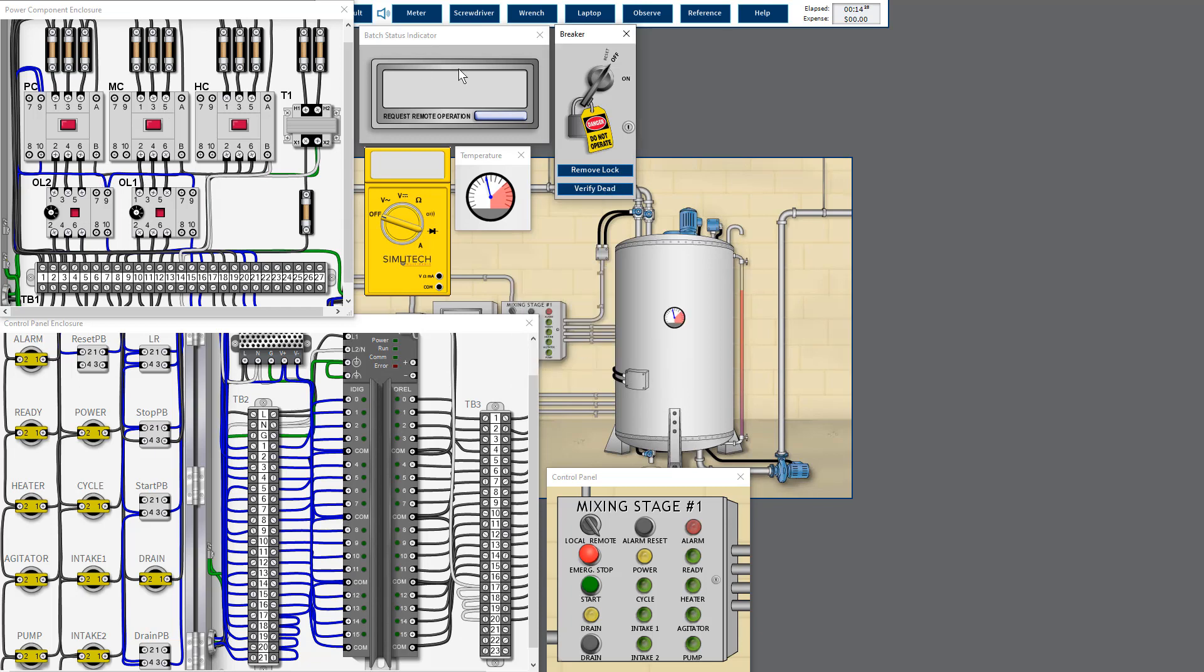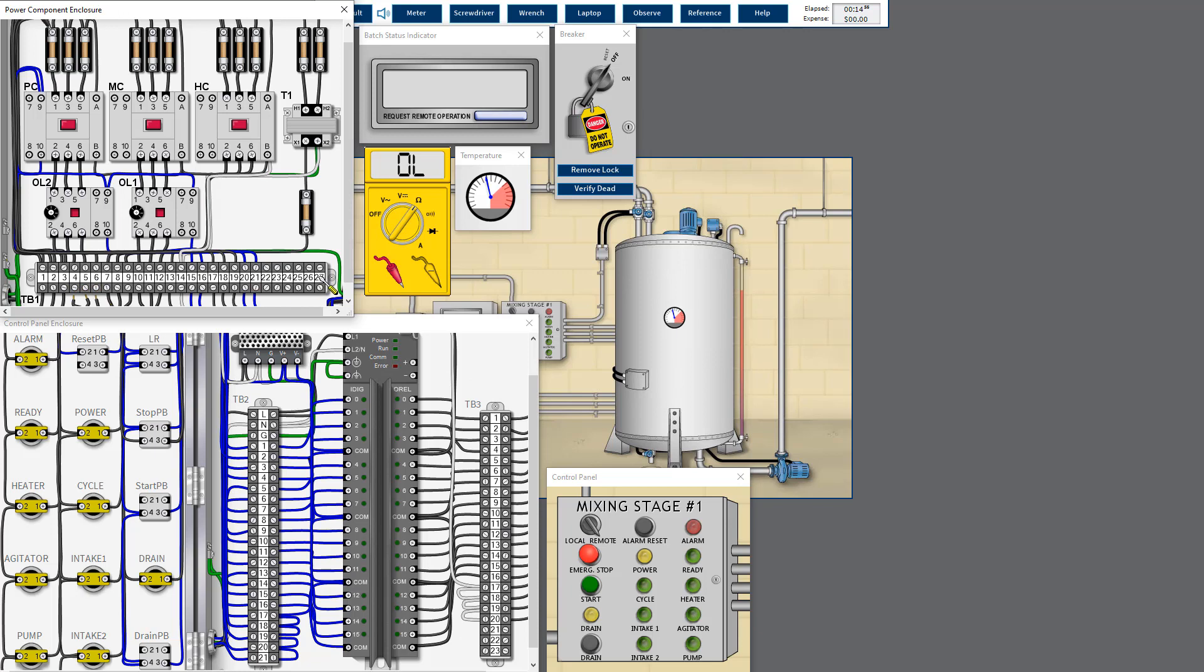First, I will usually measure the whole line all the way from the upstream of fuse towards the downstream of the overload relay. Okay, when you measure, you measure the resistance across the device with one end open, of course you can do it with two ends open. Okay, I open one end then we measure the resistance. There's an open loop, so hmm, so what's the issue here?